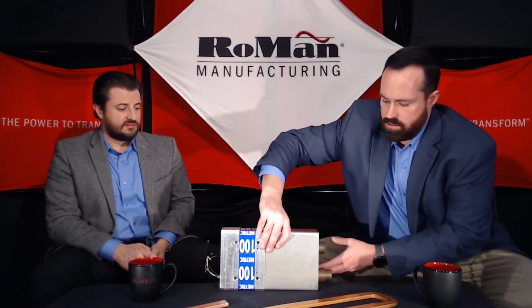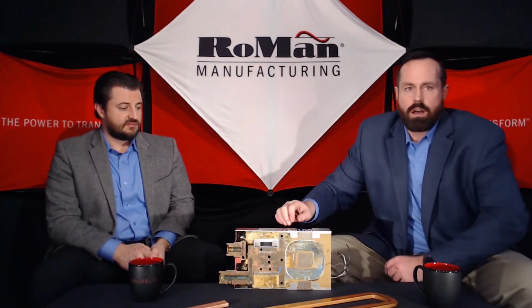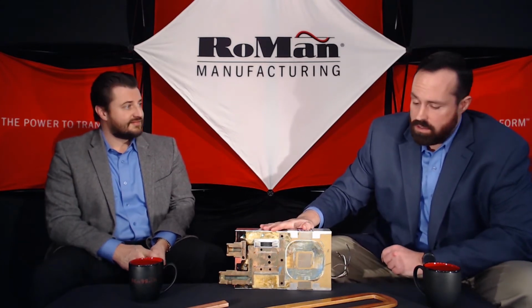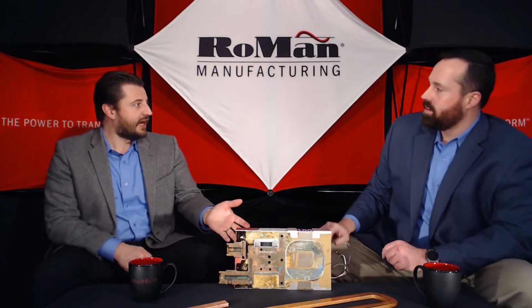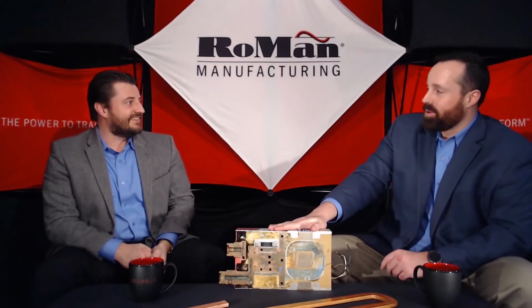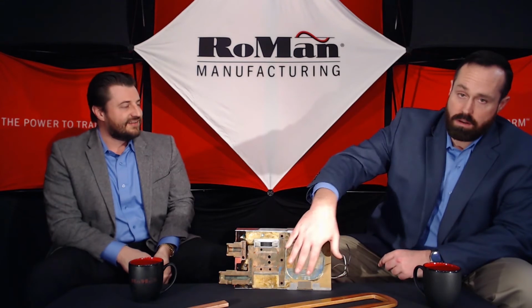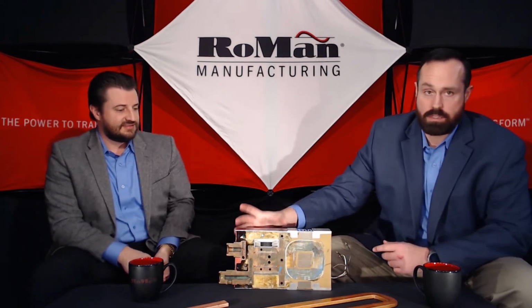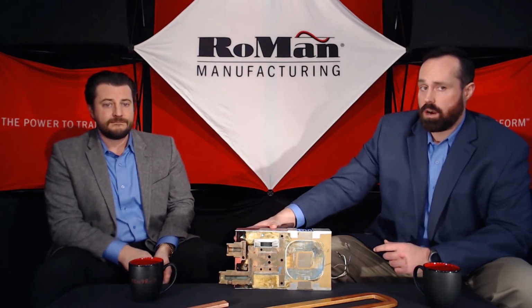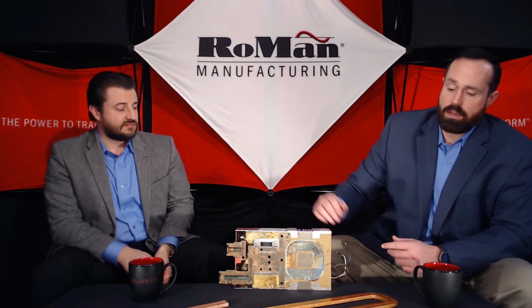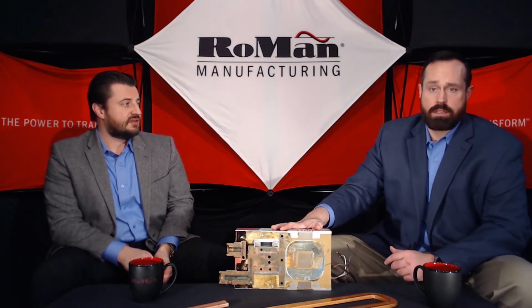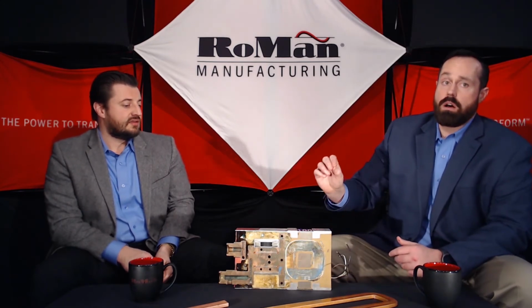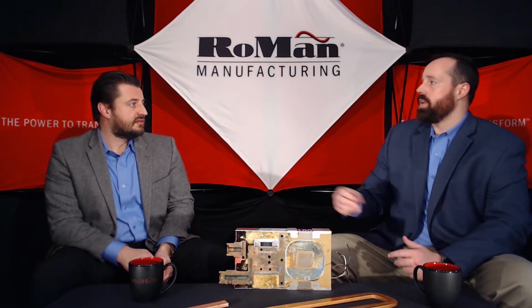So if we look inside a transformer, let's take a look inside this transformer here. So if I turn this around, this is a transformer cut in half. We don't sell them like these. We have the primary. Would you just get 50% power if you sold that? One could potentially think, but no, it doesn't work. This is not a working model. Okay. This is more for just demonstration purposes. But so we have our transformer portion of the transformer here, and then this is a portion we're going to talk about later. But this is our rectifier diode portion. But these are the turns that you would see in a transformer. So typically in a transformer this size, which is a 100 kVA transformer, we will pump approximately anywhere between 1 and 2 gallons per minute through the transformer.